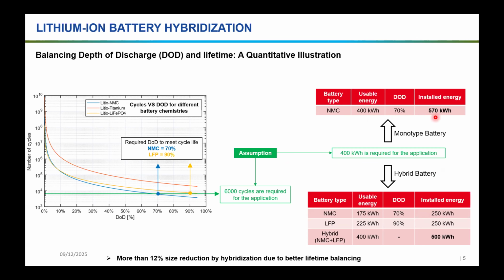We need to install 570 kilowatt hours of NMC to meet these requirements. On the other hand, if we choose a hybrid topology combining NMC and LFP, we can take 175 kilowatt hours out of this 400 from NMC, and the rest, 225, from LFP. With the mentioned DODs, we need to install 250 kilowatt hours for each of these technologies, and the combination will be 500 kilowatt hours. So by hybridization, we are able to reduce the size of the battery system by more than 12%, due to better lifetime balancing.